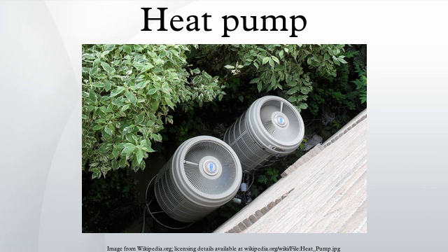Hybrid heat pumps, when outdoor air is above 4 to 8 Celsius, they use air. When air is colder, they use the ground source. These twin-source systems can also store summer heat, by running ground source water through the air exchanger or through the building heat exchanger, even when the heat pump itself is not running. This has dual advantage: it functions as a low running cost for air cooling, and it cranks up the temperature of the ground source, which improves the energy efficiency of the heat pump system by roughly 4% for each degree in temperature rise of the ground source.